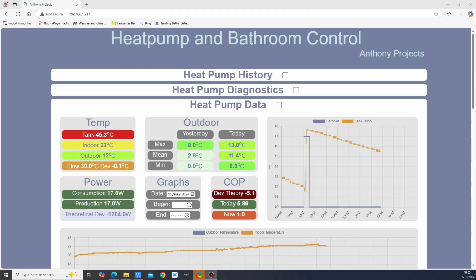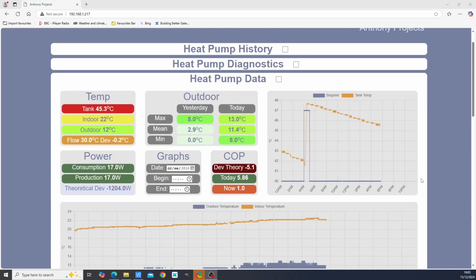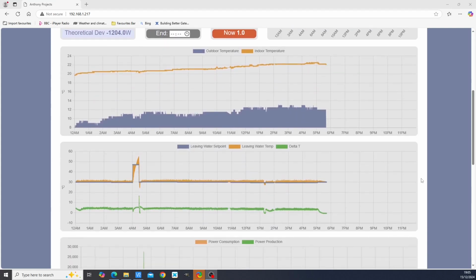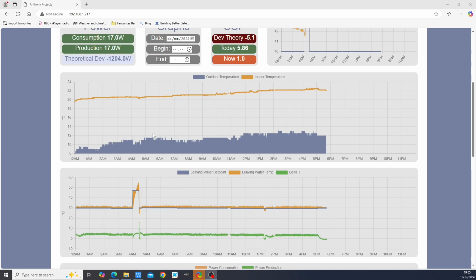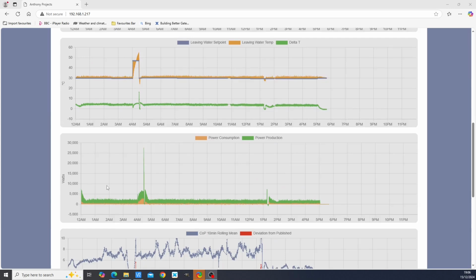You can have the set point in weather dependent mode or fixed. And what I'll need to do is change it to fixed mode for milder temperatures and then see how the heat pump reacts. So what I did was that I waited for a mild day and I set the flow temperature set point to 30 degrees. And here is our mild day. It is the 15th of December. And you can see we've got temperatures which are hitting 12.5, 13 degrees at times in the early afternoon. And what I did the day before is that I just set the flow point temperature to 30 degrees. Let's have a look, see what happened with the outputs.